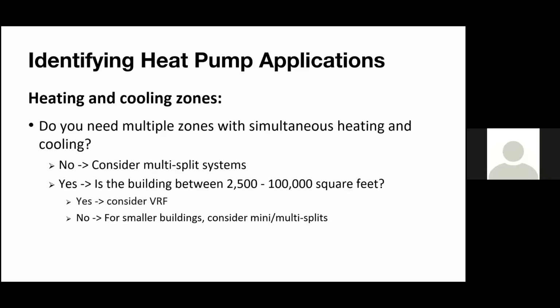So a couple questions that we need to ask ourselves have to do with zoning. Do we need simultaneous heating and cooling in certain zones? Going back to an application, let's say, a box store, for example, we could do a Walmart, Home Depot, whatever it is, right? That needs a lot of CFM, and it's really one zone or a couple little zones here and there that just have a high CFM, right? So, that might not be the best application for VRF and zoning, right?